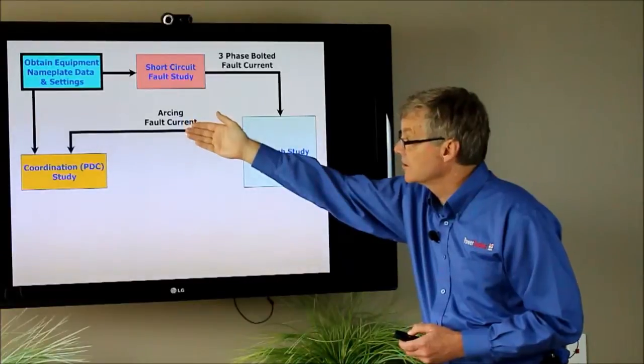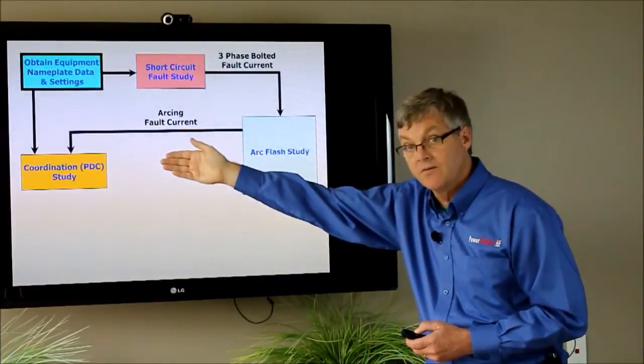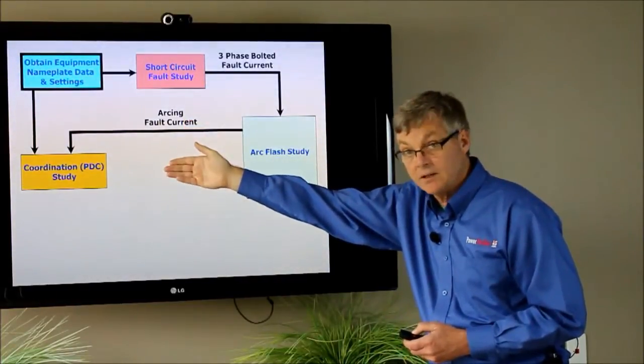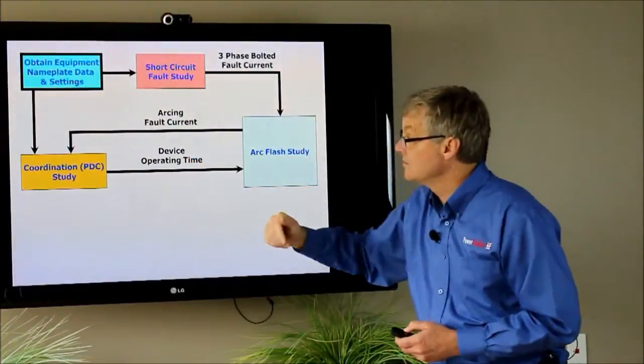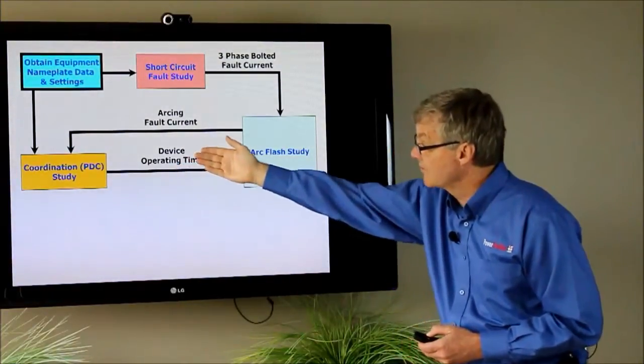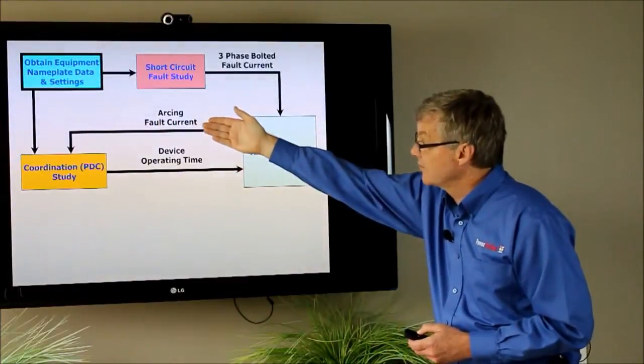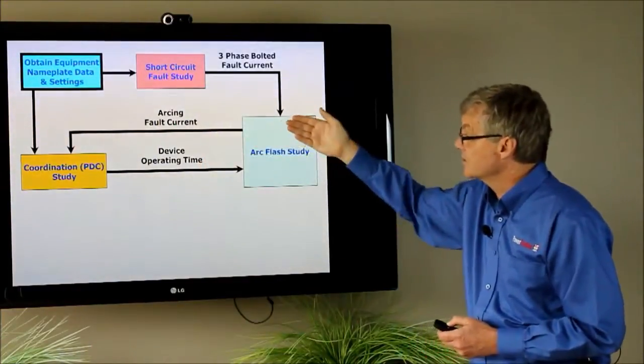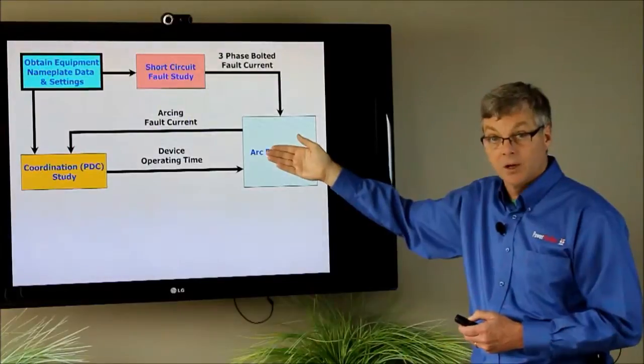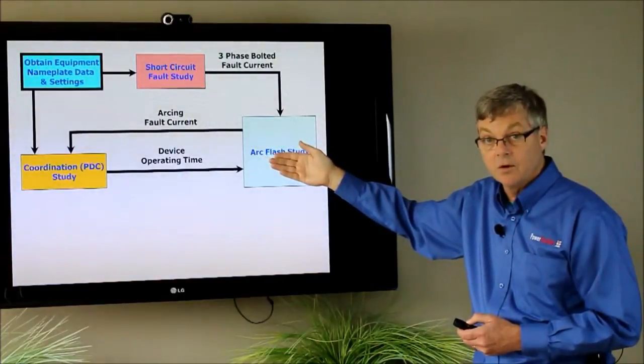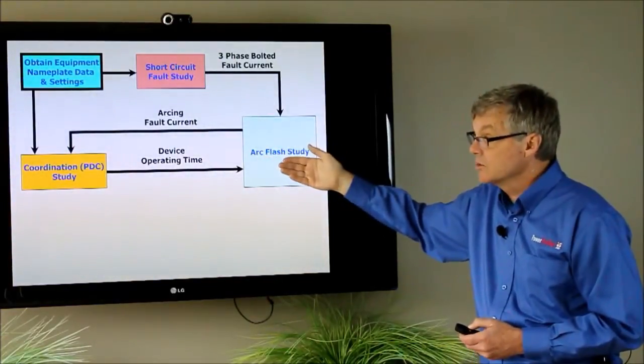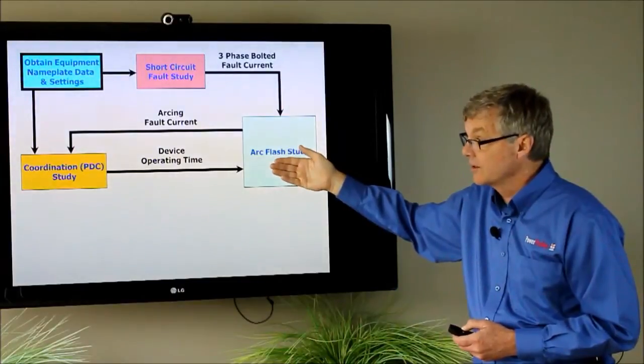Once we know what this arcing fault current is and our upstream protective device and its settings then the coordination module will give us the device operating time and once we know the arcing fault current and device operating times these numbers are plugged into the IEEE 1584 equations and the equations will then calculate the arc flash energy and the arc flash boundary.